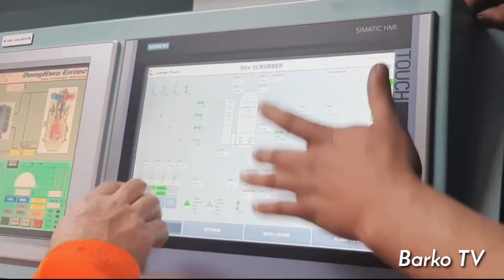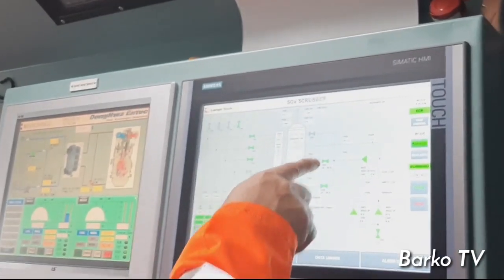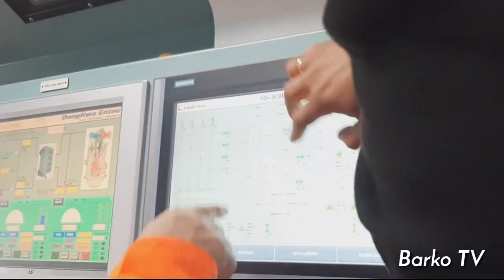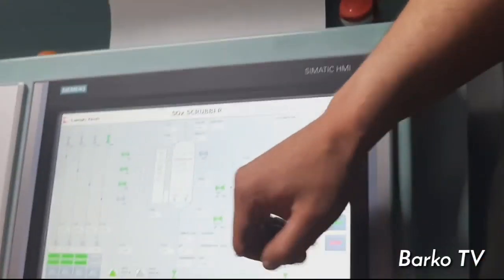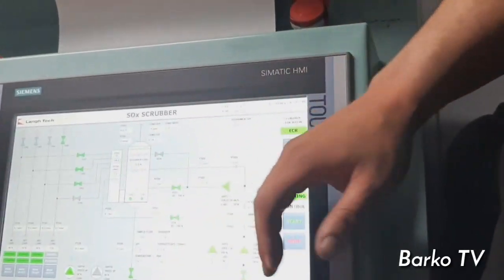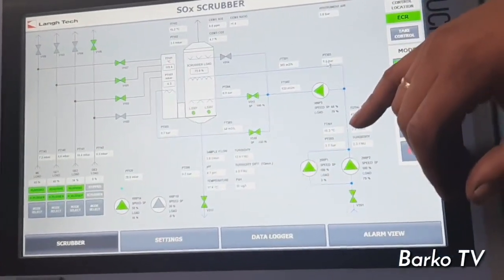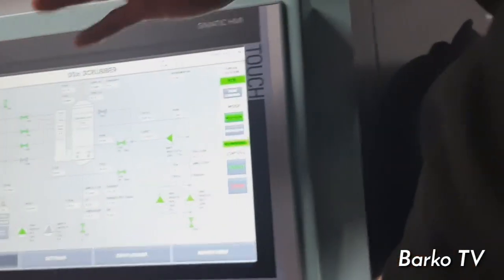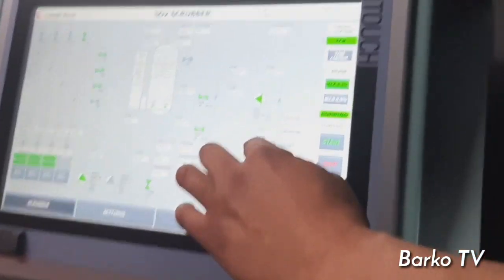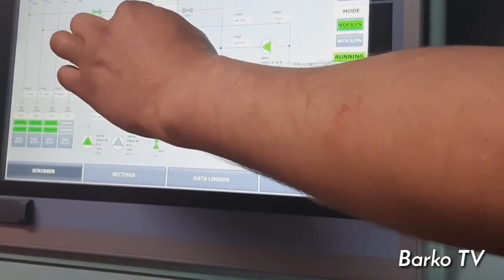We have a little blink indicating valve openings — we run and subsequently they should open. Those are already open. You can see the pumps start as needed. Right now there are two running because we are at 66-65% load. With a correction factor of around 0.1 you can run with one pump up until 64-65% load. After that the system needs two pumps — the other one will start up also. Water goes up to the washing nozzles.